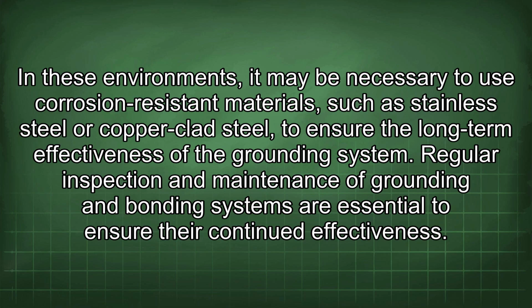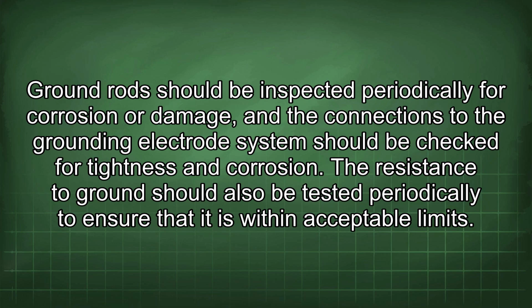Regular inspection and maintenance of grounding and bonding systems are essential to ensure their continued effectiveness. Ground rods should be inspected periodically for corrosion or damage, and the connections to the grounding electrode system should be checked for tightness and corrosion. The resistance to ground should also be tested periodically to ensure that it is within acceptable limits.